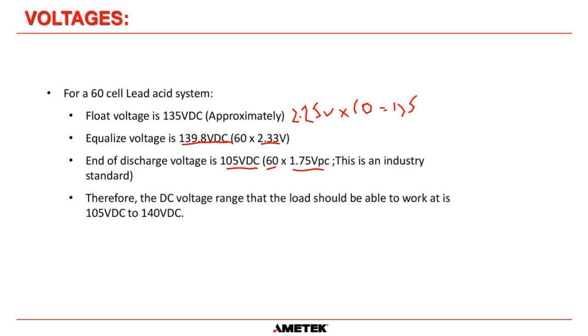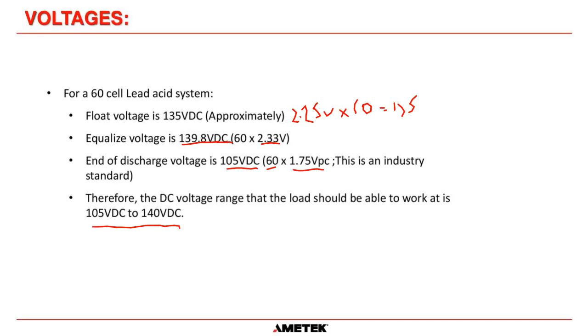So if this is connected to a switchgear system, the relays and all the associated parts of your switchgear system must be able to handle between 105 volts and 140 volts DC. And in truth, that should be the case because it's an industry standard.